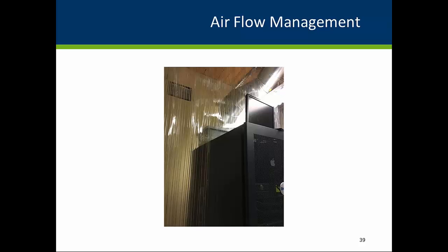An especially interesting example of this was provided at the site that used a 750 CFM exhaust fan to remove heat from the server room. The fan drew about 300 watts. Conditioned air was drawn from the rest of the office through a grate in the door. The power load of the SEDC was about 4 kilowatts, and server inlet temperatures reached as high as 86 degrees.